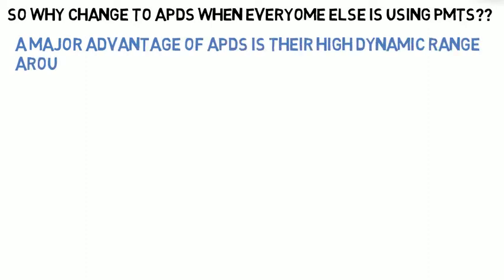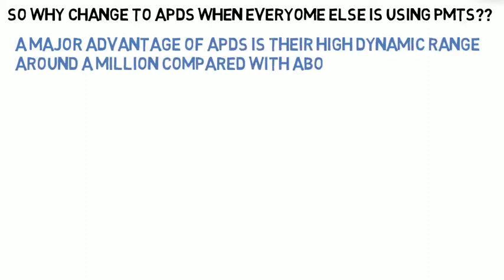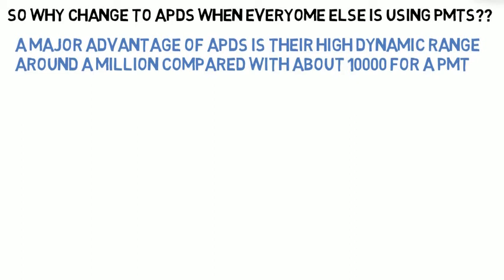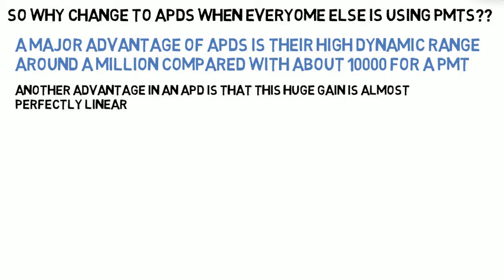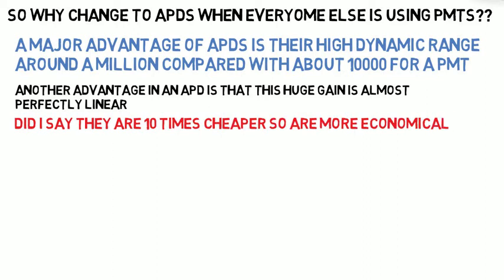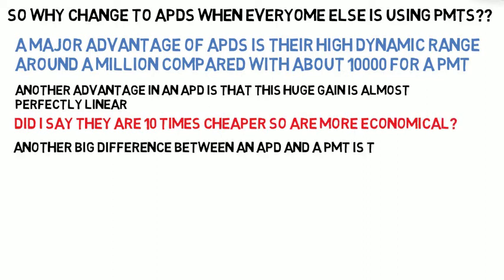A major advantage of APDs is the high dynamic range — around a million — compared with about 10,000 for a PMT. Another advantage is that this huge gain is almost perfectly linear. And they're 10 times cheaper than PMTs.